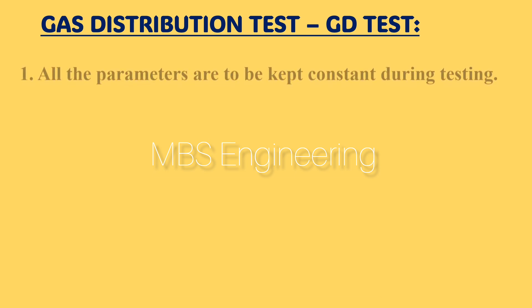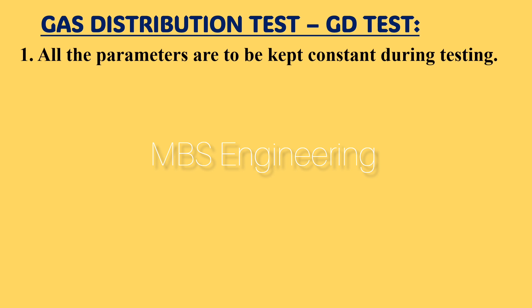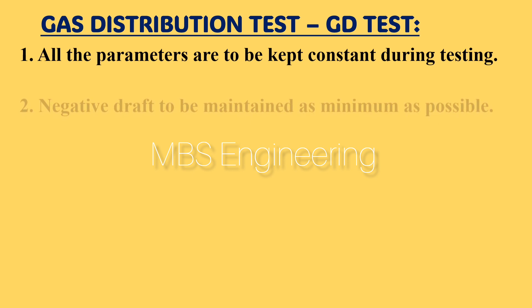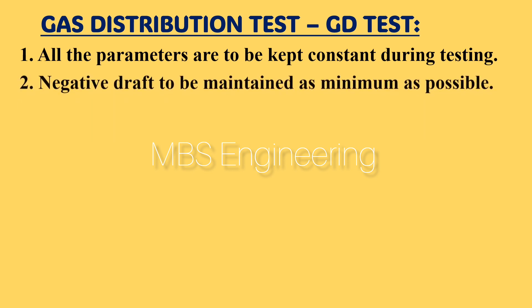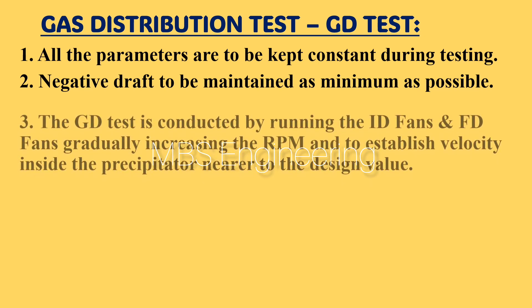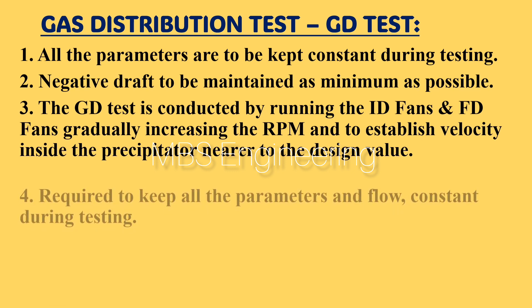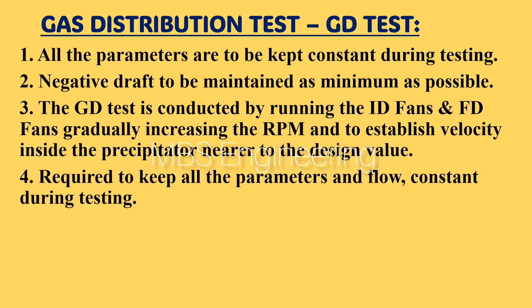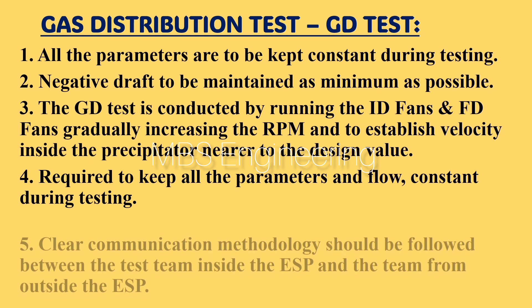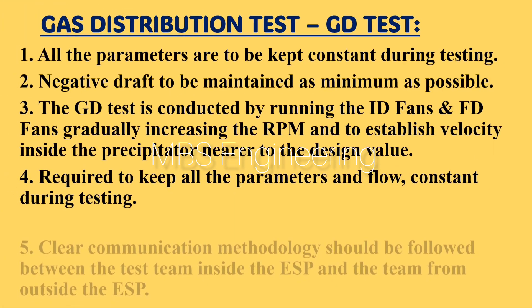GD test procedure: Point 1: all parameters are to be kept constant during testing. Point 2: negative draft is to be maintained as minimum as possible. Point 3: the GD test is conducted by running the ID fans and FD fans, gradually increasing the RPM to establish velocity inside the precipitator nearer to the design value. Point 4: all parameters and flow must be kept constant during testing. Point 5: clear communication methodology should be followed between the test team inside the ESP and the team outside.